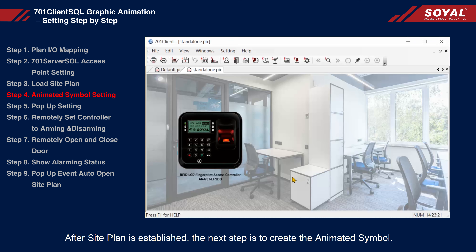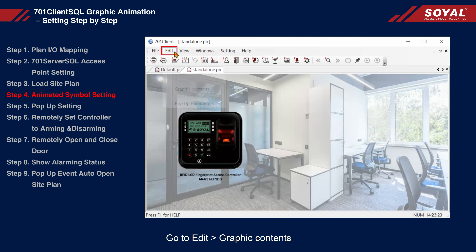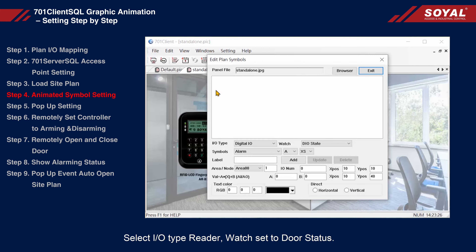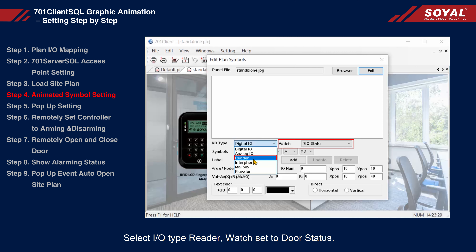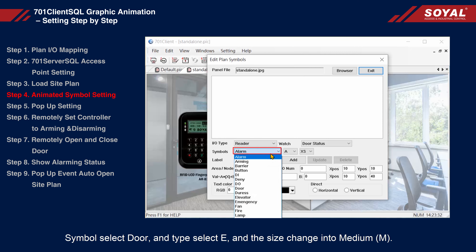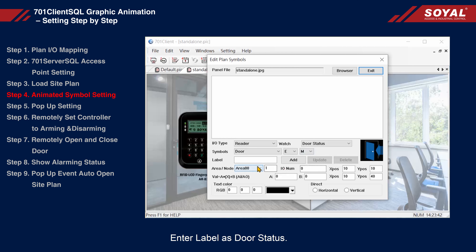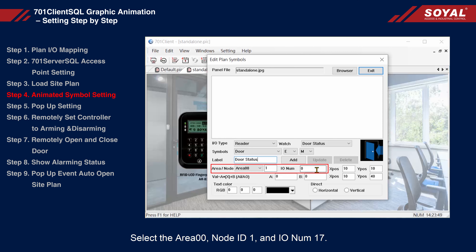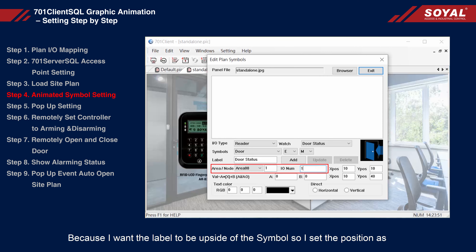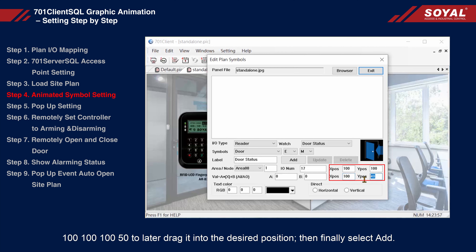Go to Edit and select Graphic Contents. Select I/O type: Reader, set Watch to door status, symbol set to Door, and type select E. Change the size to medium (M). Enter the label as 'door status'. Select area 00, node ID 1, and I/O number 17. Because I want the label to be above the symbol, I set the position as 100, 100, 100, 50, to later drag it into the desired position, and then click Add.